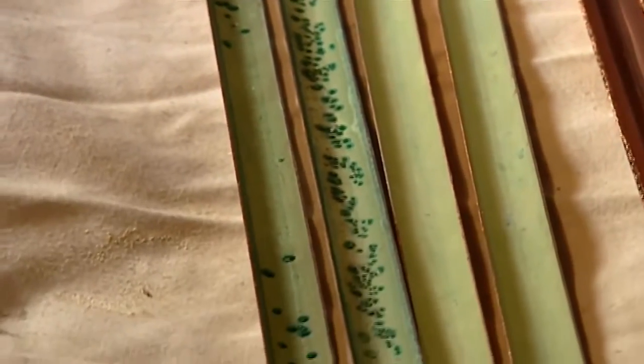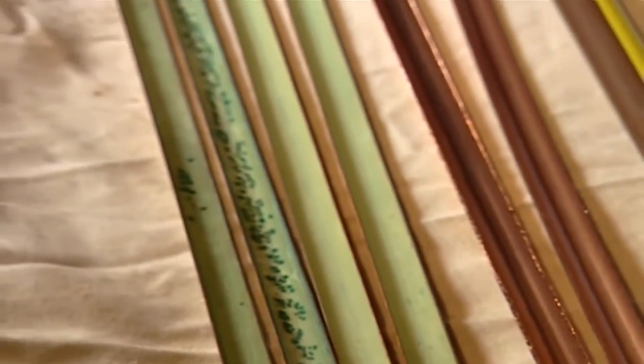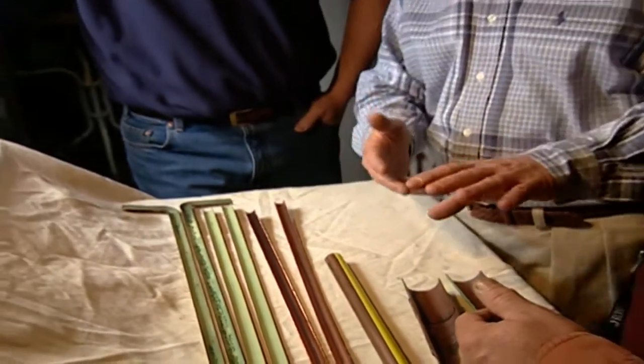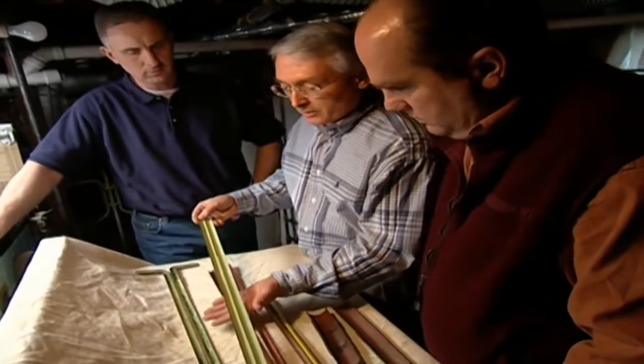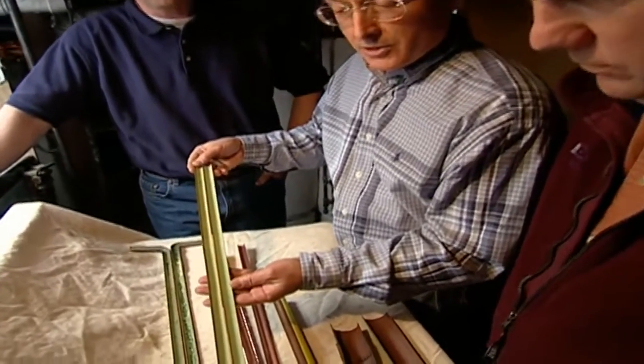That's right. Now, you mentioned something about cold or hot water pipe being more prevalent? Cold water issues are much more prevalent. The reason being is in hot water systems, if you had excessive flux, the heat of the water melts it and carries it away. It would dissolve it, right. This section of pipe is a companion to our cold water sample, and it shows that there are no pits on the inside and the surface is very smooth. Difference. So with that, what do you think my situation is?